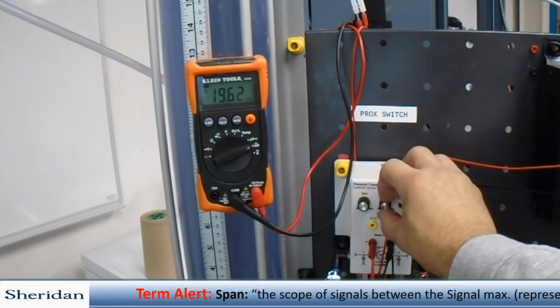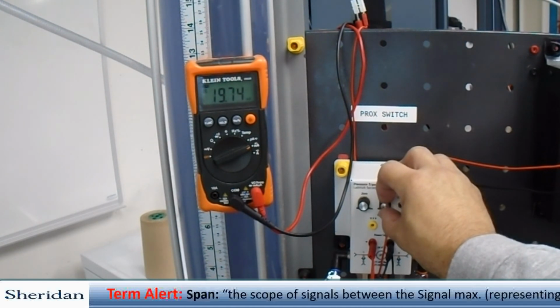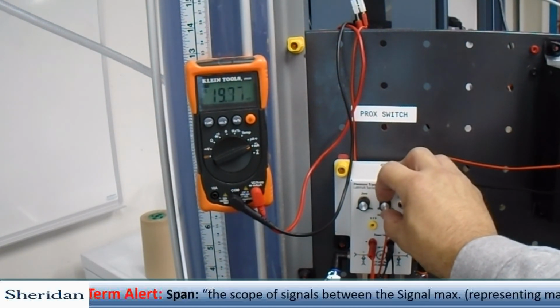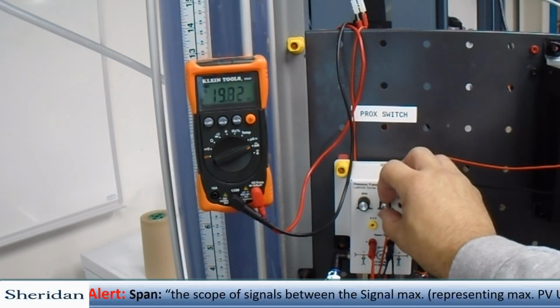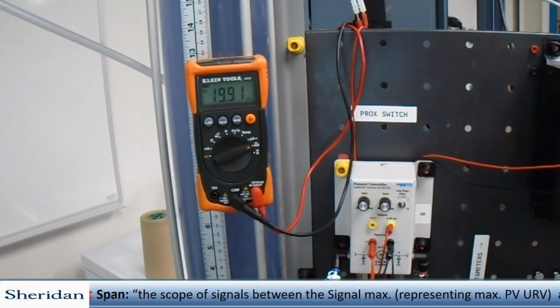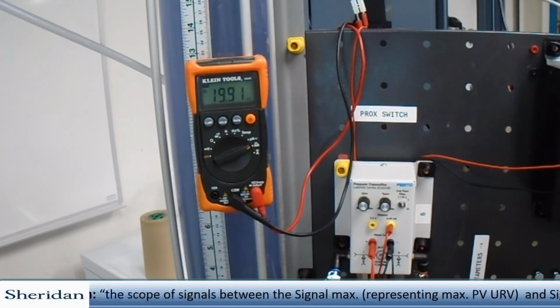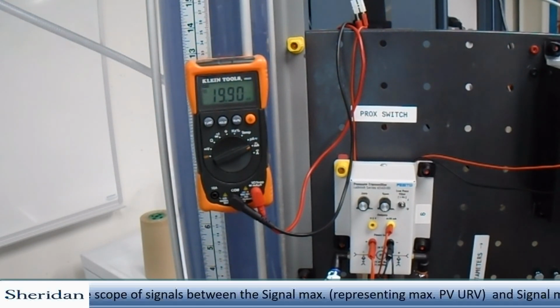You'll do this about 3 times until you get it as close to 20 as possible and as close to 4 without going beyond those. So I'm at 19.91. Go check our zero again.